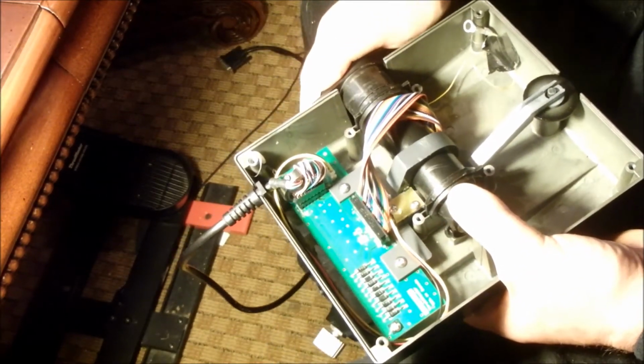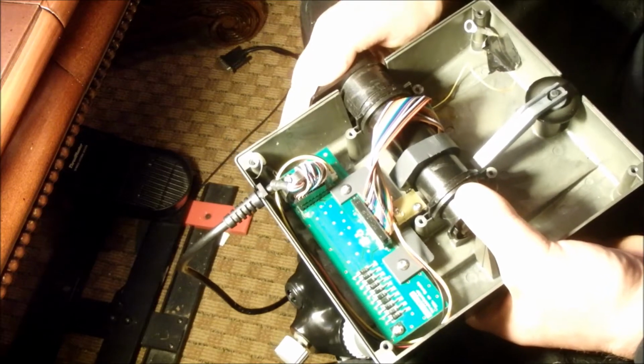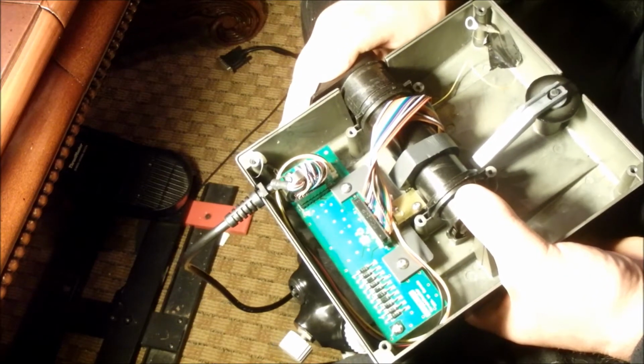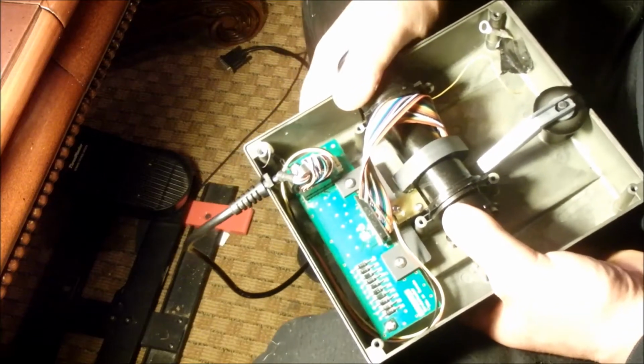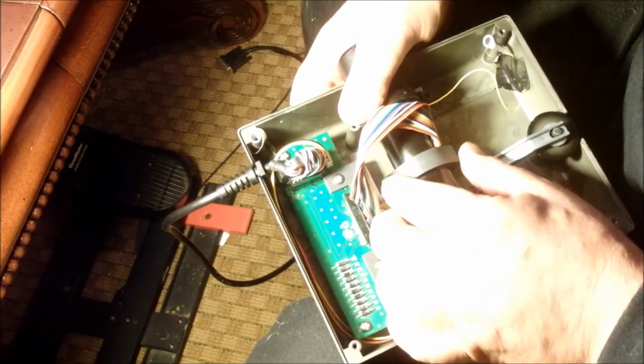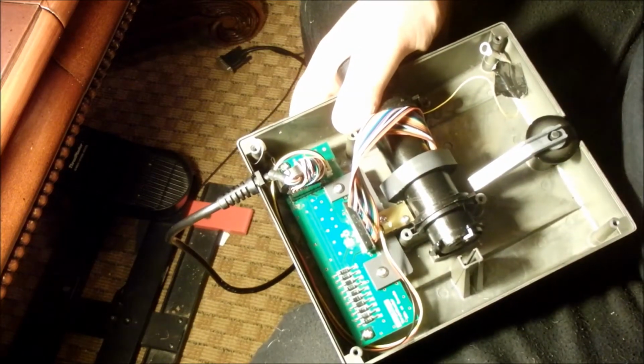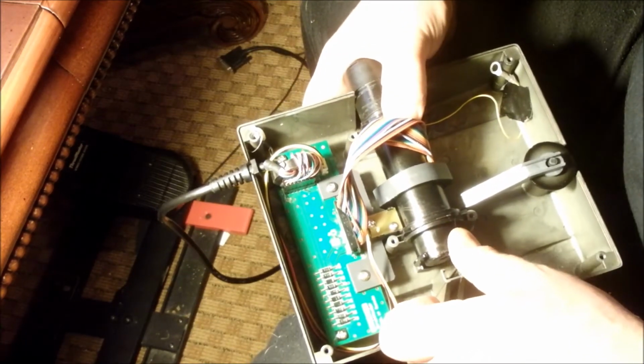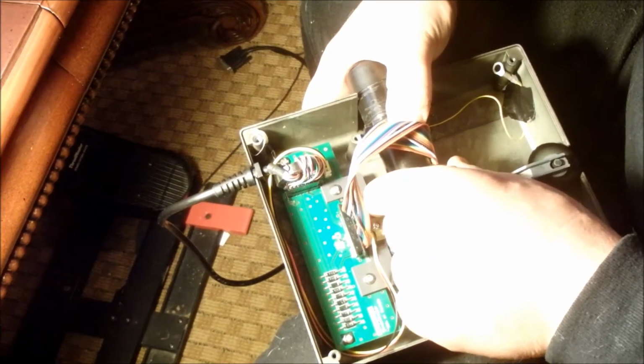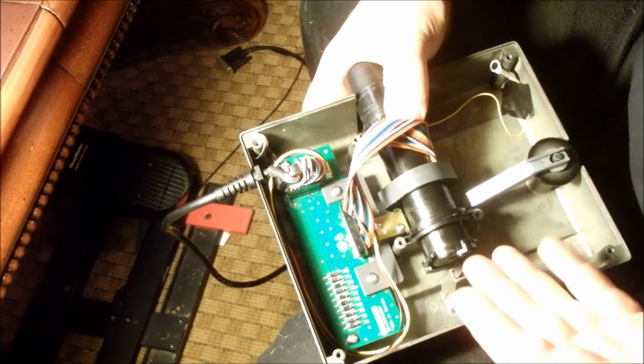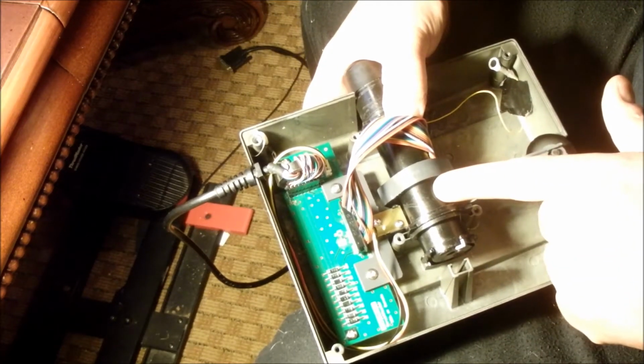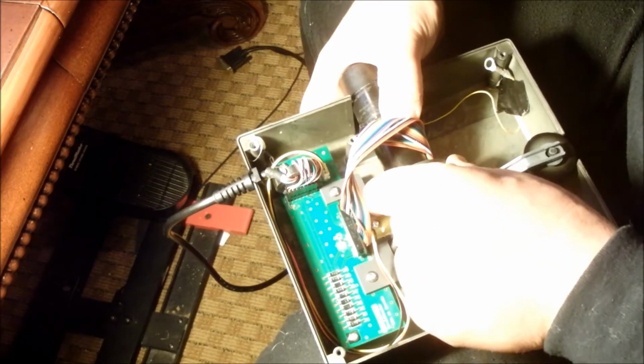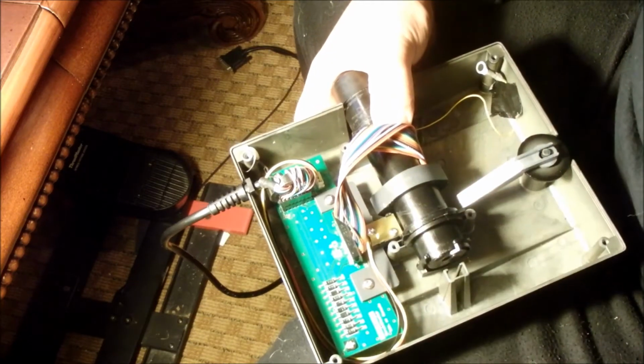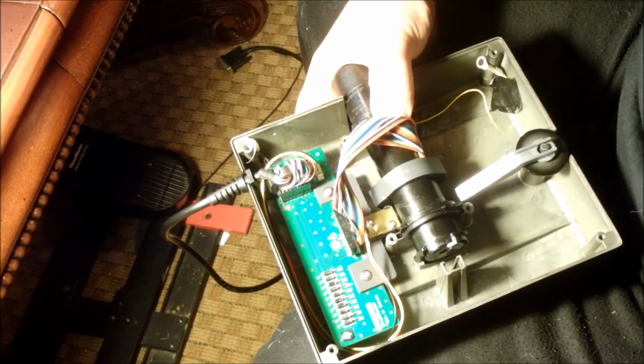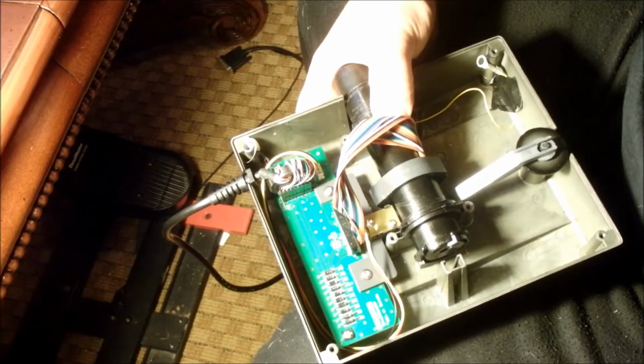Same thing, because it's so close and the magnetic field is so powerful, we're actually having dead space at the top end also. So what we're going to do is we want to reduce that magnetic field, and we're going to do that by sliding the sensor back slightly. Our starting point is always the same, which is all the way down against the case. We don't want to do it so far that it starts lifting up the actual handle, but we want it to be bottomed out against the case. And the number seems to be about 3/16, which is going to be anywhere between 15 and 20% on your raw score on your DI view.